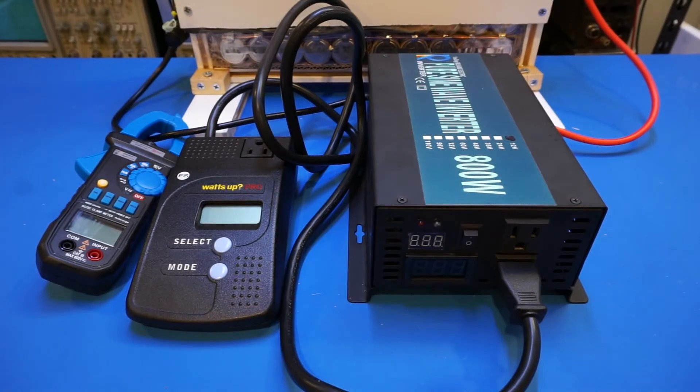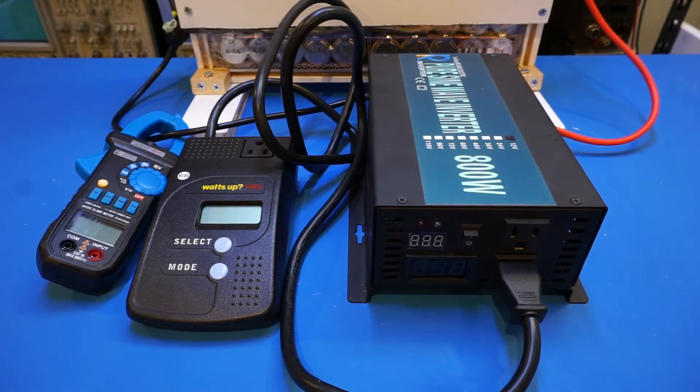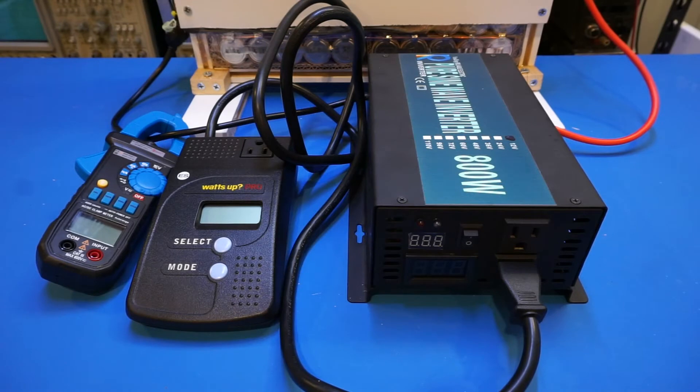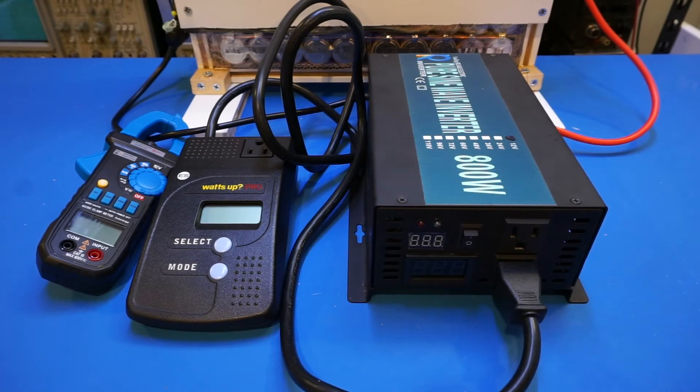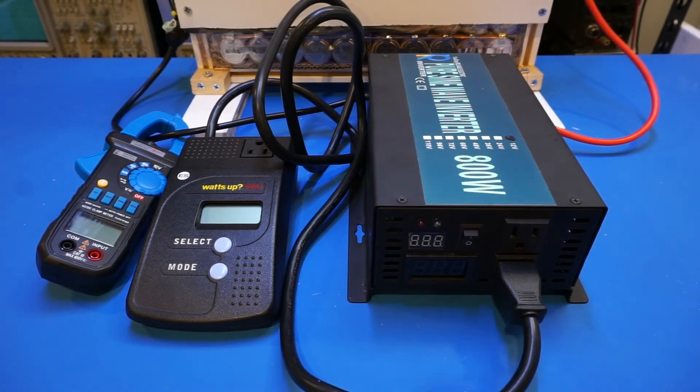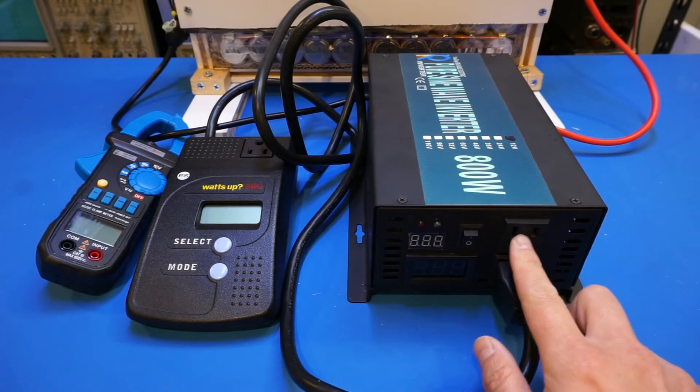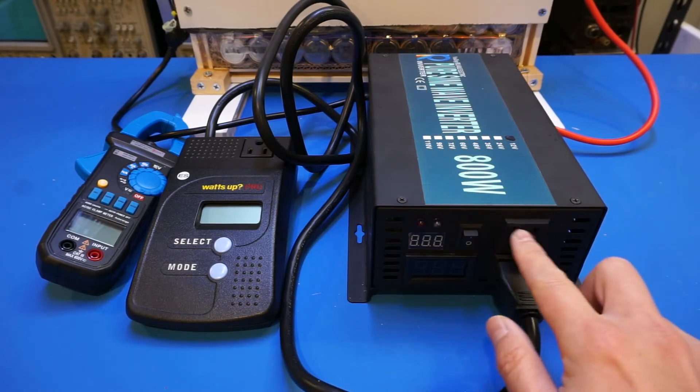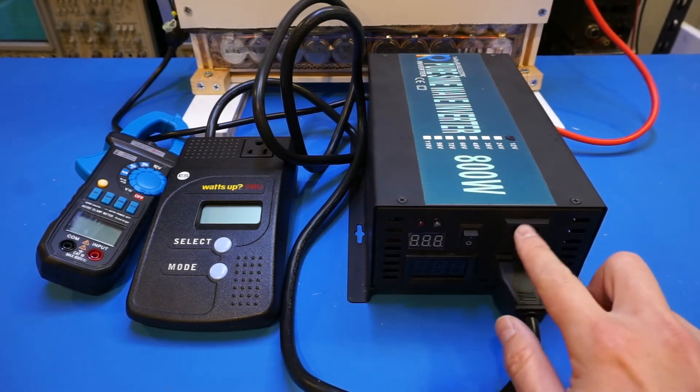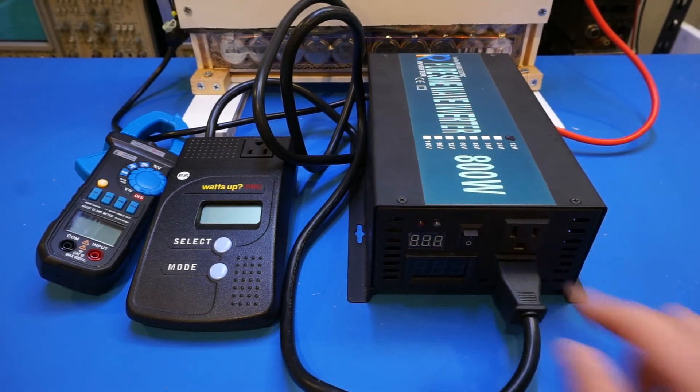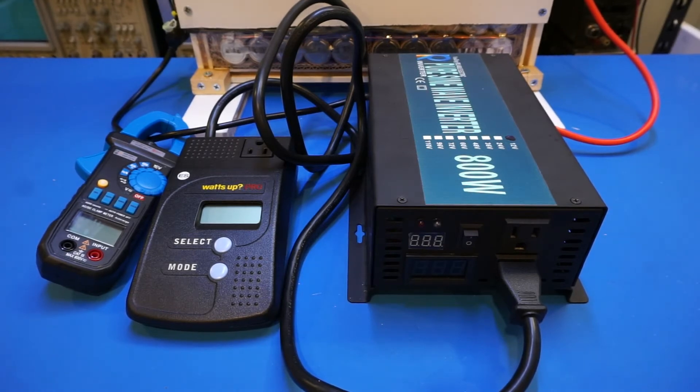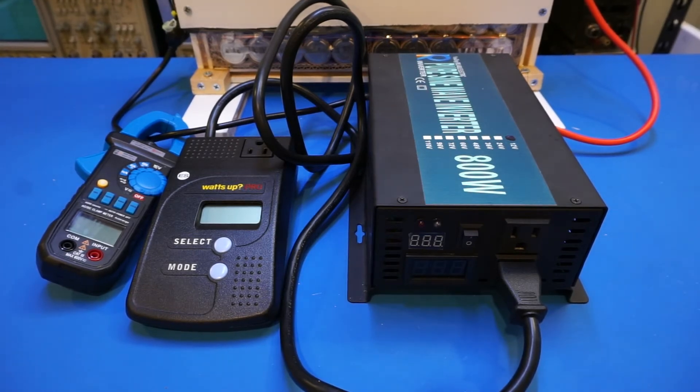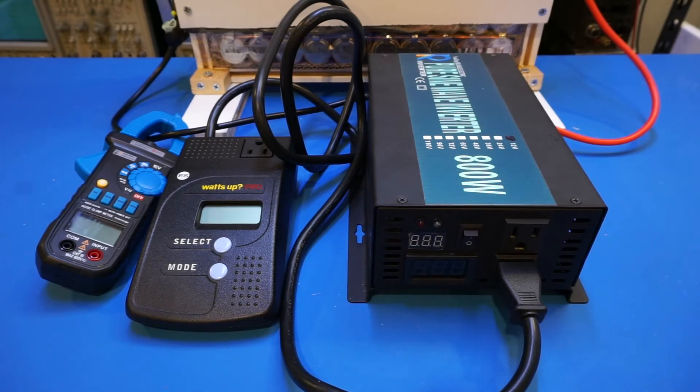Okay, now we are back in the lab and that cable itself is about 10 feet too short to reach this bench. So I might need an extension cable to get it working. But before doing that, you notice that we have a standard 3-prong outlet. And the generator transfer panel uses a L14-30R type of NEMA connector. So how do we actually make this connection?